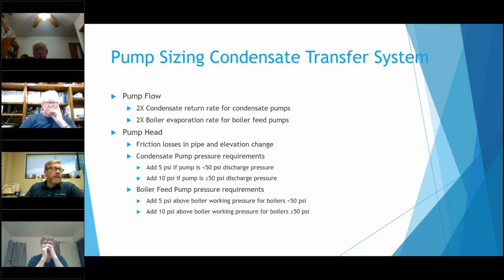But after you figure out the pipe loss, you do want to add, depending on whatever that discharge pressure on the condensate pump is. If it's under 50, you want to add 5 pounds to it just for a little safety factor. If it's above 50, you want to add 10.